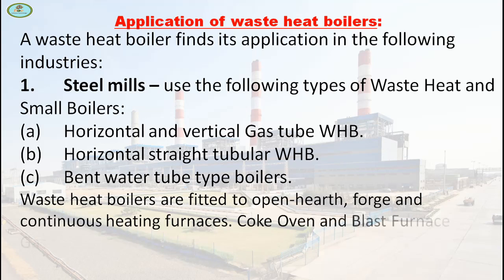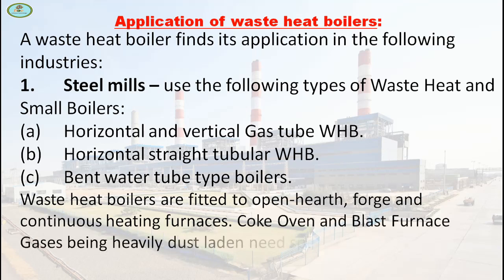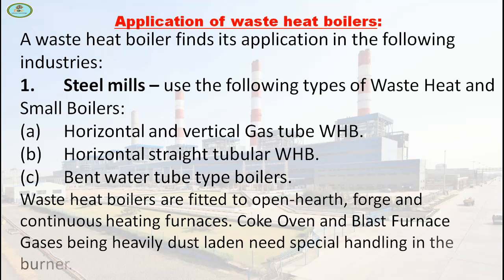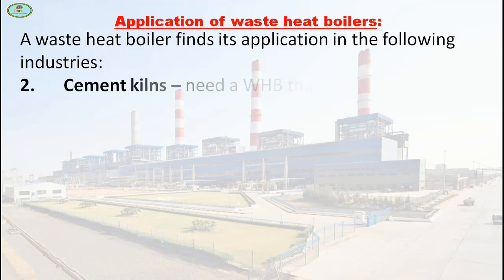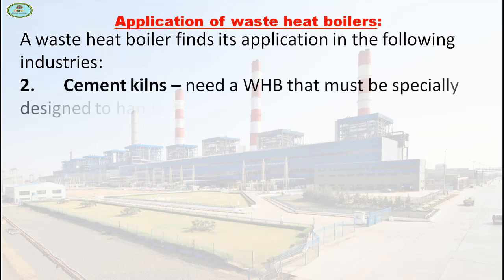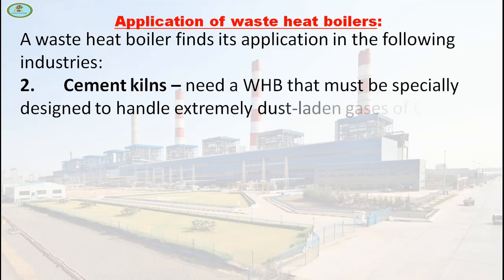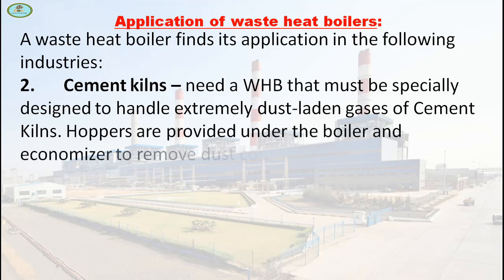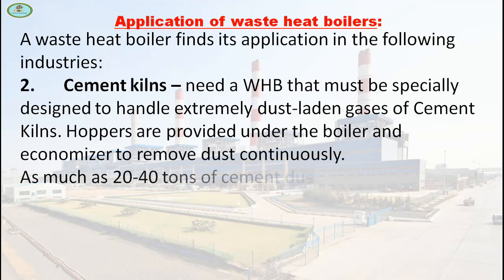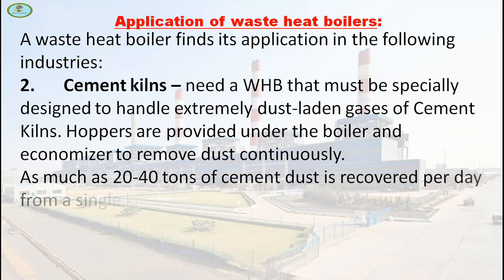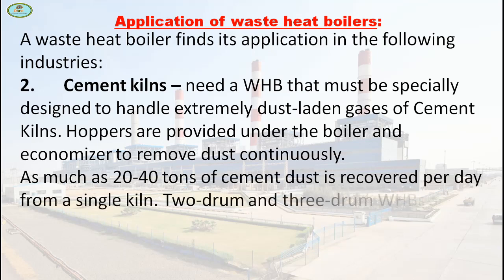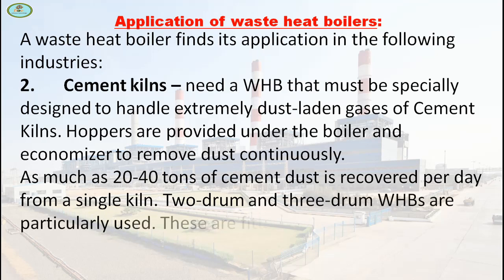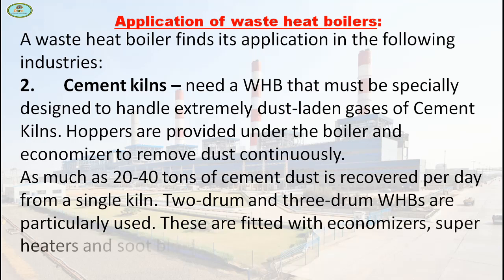Coke oven and blast furnace gases, being heavily dust-laden, need special handling in the burner. Next is cement kiln. A WHB must be specially designed to handle the extremely dust-laden gases of a cement kiln. Hoppers are provided under the boiler and economizer to remove dust continuously. As much as 20 to 40 tons of cement dust is recovered per day from a single kiln. Two-drum and three-drum WHBs are particularly used, fitted with economizer, superheaters and soot blowers.